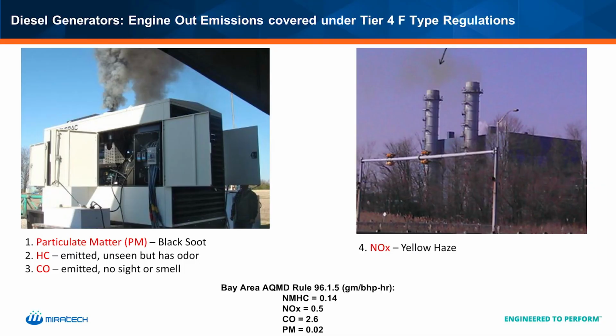Really, what we're looking at are four constituents coming out of a diesel engine, covered under the Tier 4 type regulations. There's particulate matter, the black soot you'd commonly see coming out of an engine. There's hydrocarbons, which are emitted but not seen, though you may smell some odor. There's CO, which has no sight or smell. And the fourth item is NOx, commonly referred to as the yellow haze you may see coming from a power plant running.